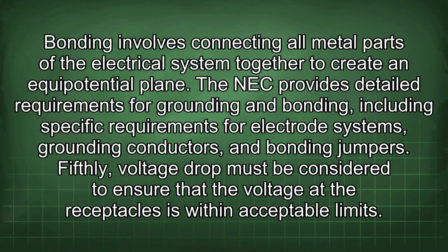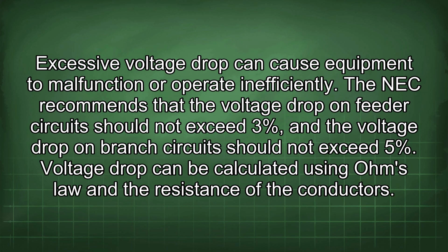Fifthly, voltage drop must be considered to ensure that the voltage at the receptacles is within acceptable limits. Excessive voltage drop can cause equipment to malfunction or operate inefficiently. The NEC recommends that the voltage drop on feeder circuits should not exceed 3% and the voltage drop on branch circuits should not exceed 5%.